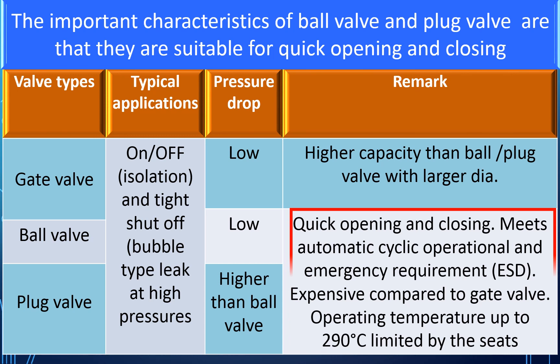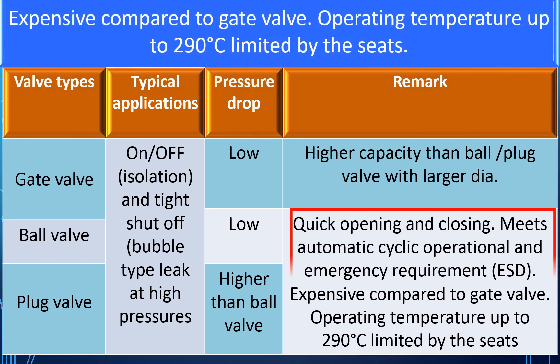The important characteristics of ball valves and plug valves are that they are suitable for quick opening and closing, and they meet automatic cycle operational and emergency requirements. They are more expensive compared to gate valves. Operating temperatures are limited to up to 290 degrees centigrade, limited by the seats.